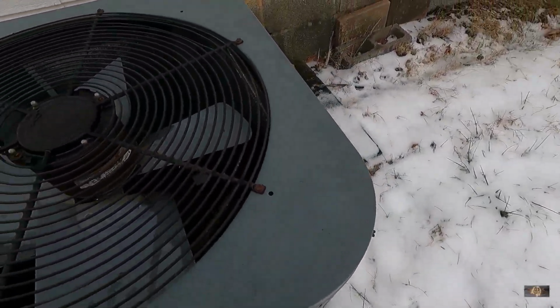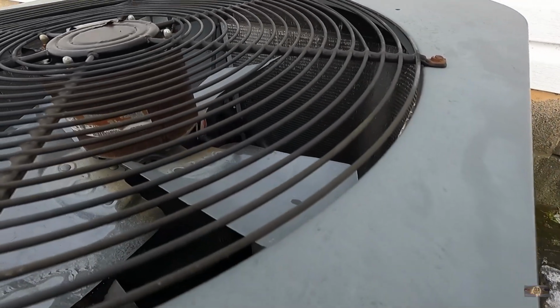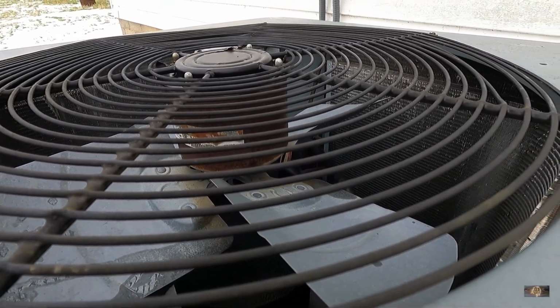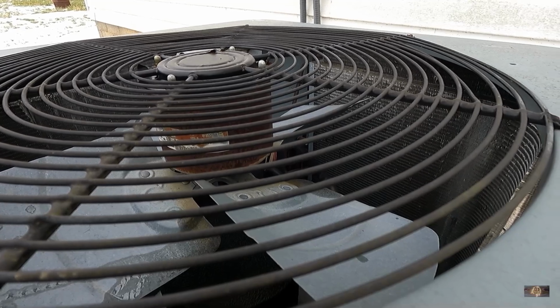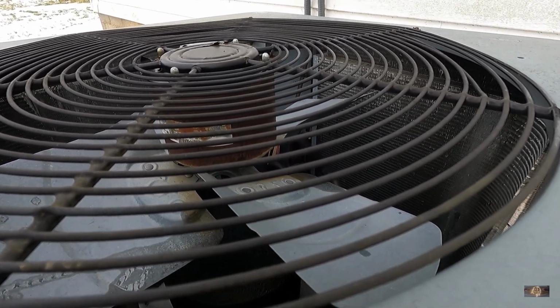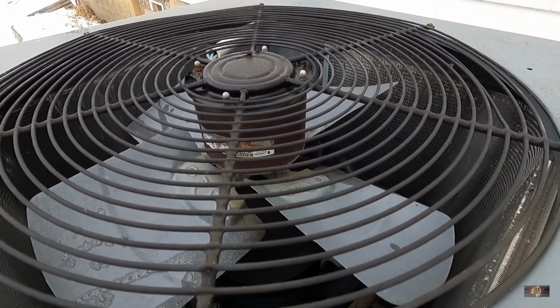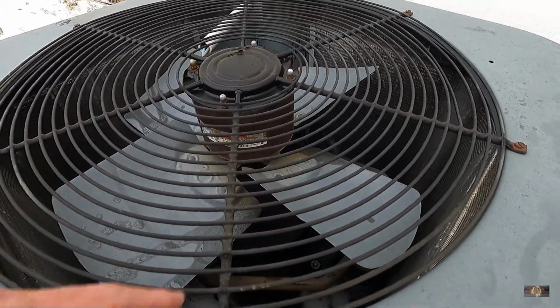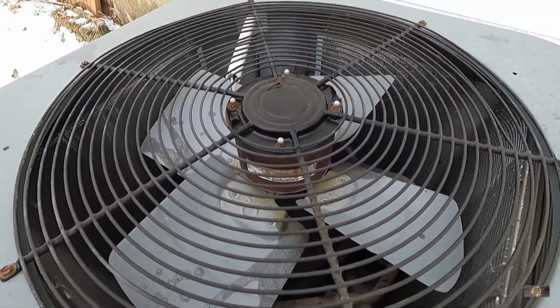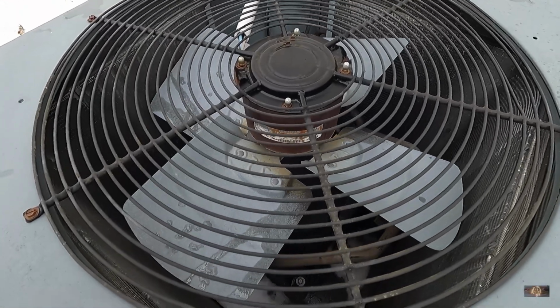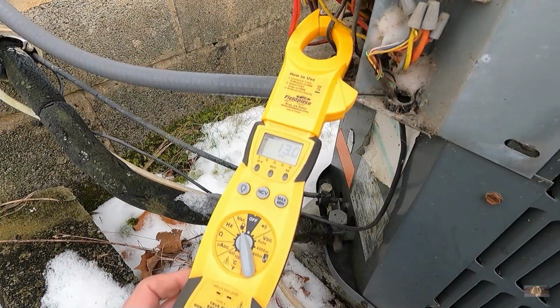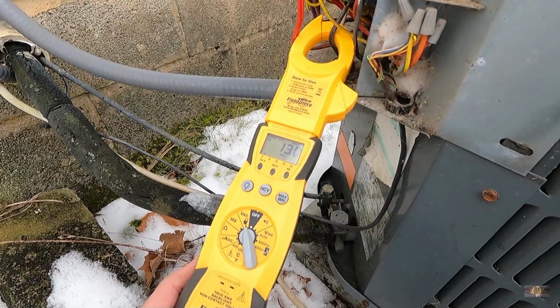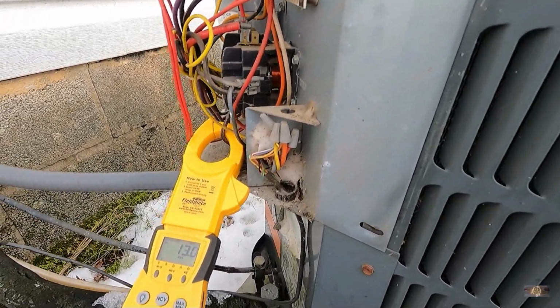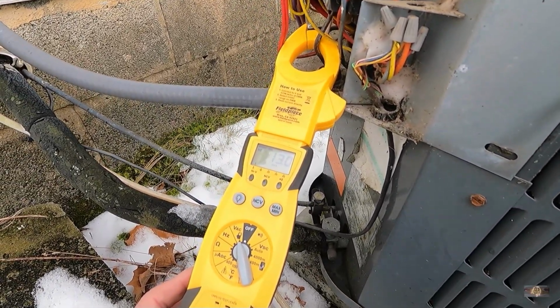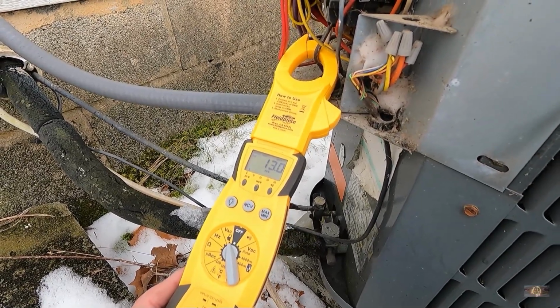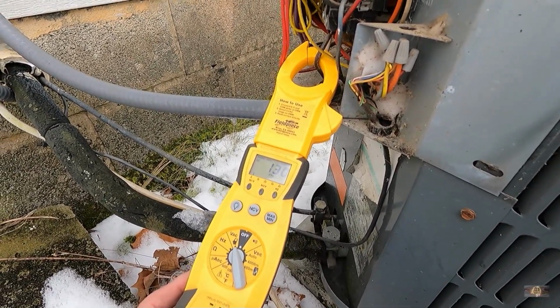What size motor is this? Looks like it's a 1/6 horsepower, 0.9 amps, 815 RPM. So if we have to replace the motor, I've probably got one in my van that'll work. I'll have to cut the shaft on it though, if it is that. Alright, I'm going to have them fire it up and see what it sounds like. Well, I just had the customer turn on the thermostat to heat. I was walking back around, I heard it start and then turn right back off. Don't know if maybe she accidentally turned it back off and now we're in a time delay.